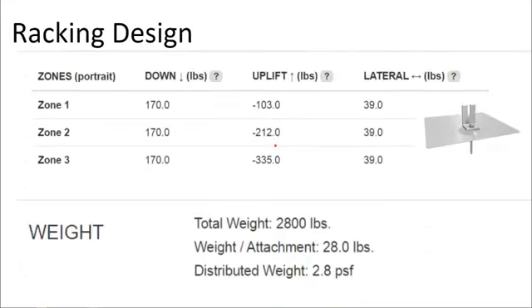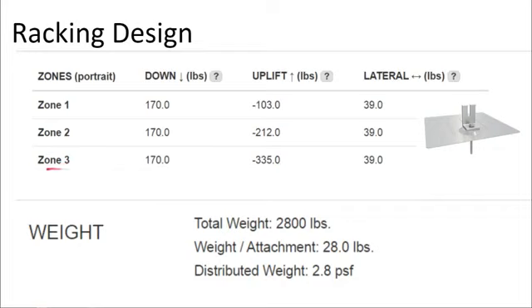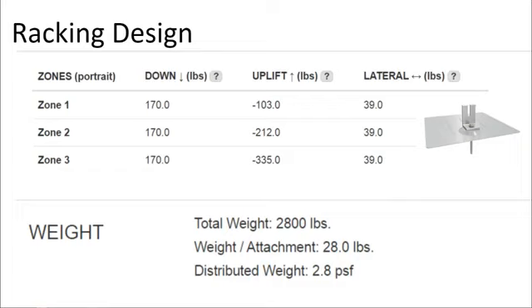Moving along in the software, the array layout, location, and attachment spacings are inputted and numbers are crunched to provide downward, uplift, and tangential forces on each attachment. In this example there is a downforce of 170 pounds and an uplift force of 100 pounds. The corners of the roof experience forces three times that amount. Moving the solar array a few feet from the exterior perimeter reduces the load, but the corners of the solar array will still experience greater wind load than the interior.